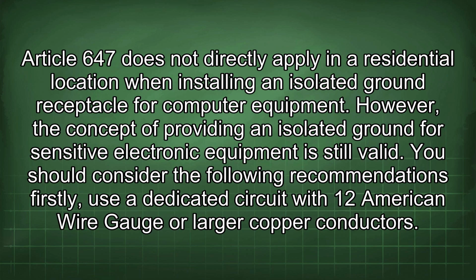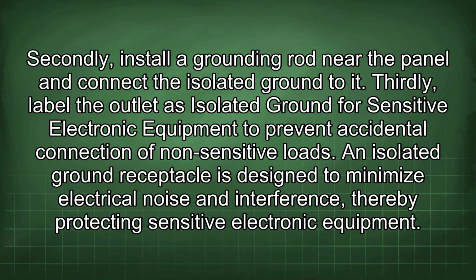Article 647 does not directly apply in a residential location when installing an isolated ground receptacle for computer equipment. However, the concept of providing an isolated ground for sensitive electronic equipment is still valid. You should consider the following recommendations. Firstly, use a dedicated circuit with 12 American wire gauge or larger copper conductors. Secondly, install a grounding rod near the panel and connect the isolated ground to it. Thirdly, label the outlet as isolated ground for sensitive electronic equipment to prevent accidental connection of non-sensitive loads.